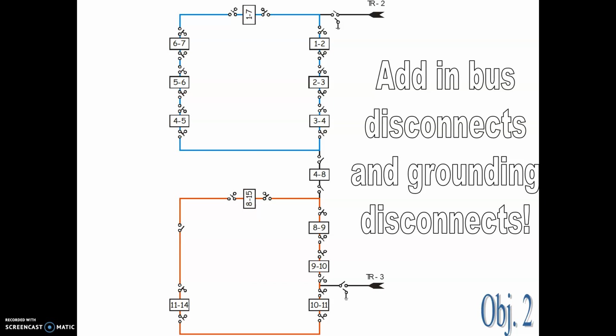So it's very important to make sure that as an operator, you're operating the right pieces of equipment. Now you'll notice that there is a difference on our drawing between some of the circuit breakers and their disconnects. This disconnect, for example, is 345 kV bus 8-15 disconnect. You'll notice it has a little line and a circle drawn off the disconnect. That symbol represents the fact that that disconnect is a motor-operated disconnect, whereas the disconnect over here on bus 1114 is a manually operated disconnect. It does not have a motor.